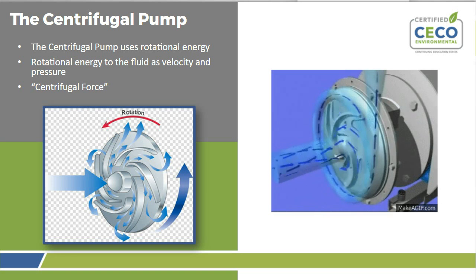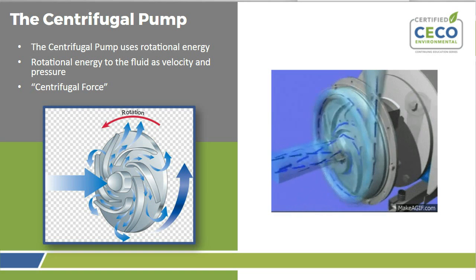The diagram basically shows the path that the fluid follows through the impeller of the pump. It enters through the center, the rotating impeller, then the vanes of that impeller impart a pressure onto the fluid, and the fluid is then expelled out the periphery of the impeller.